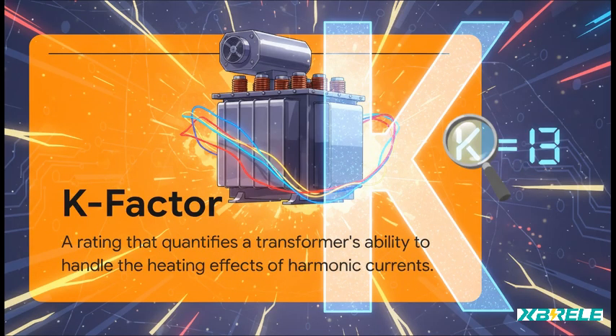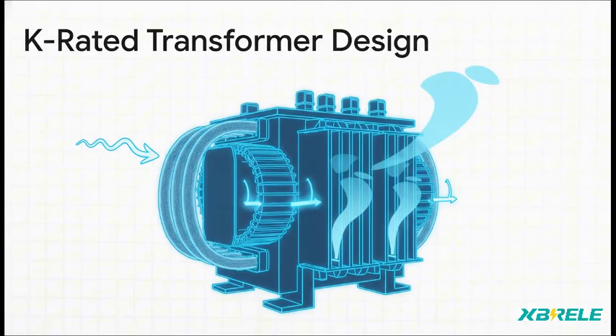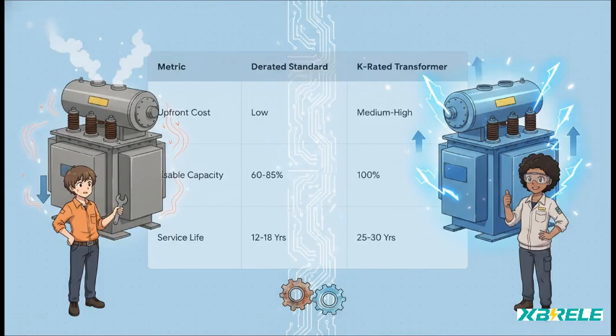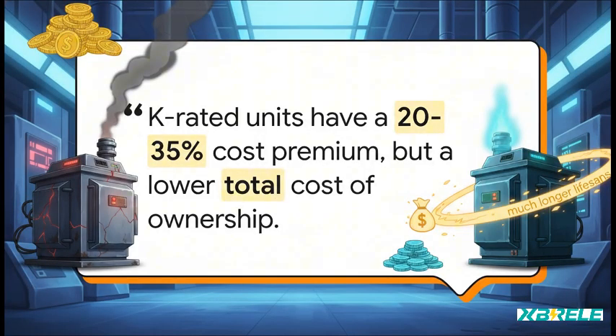Well, that brings us to the K-factor rating. Transformers with a K rating are built differently. They're designed specifically to handle this harmonic heat. So you've got two choices. Run a standard transformer way below capacity, or just get a K-rated one. Yeah, the K-rated one costs more upfront, but its total cost of ownership is way, way lower.